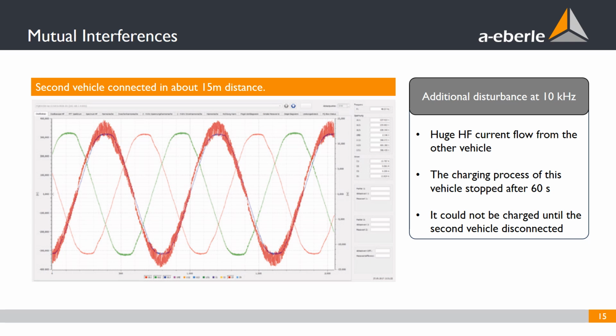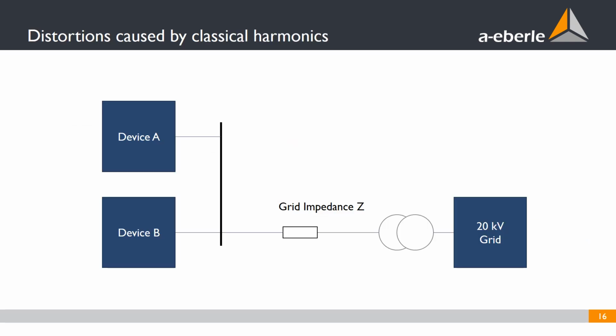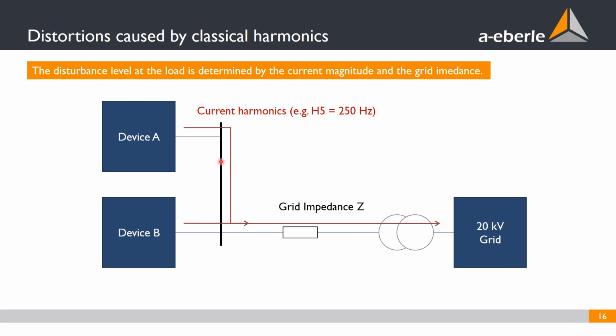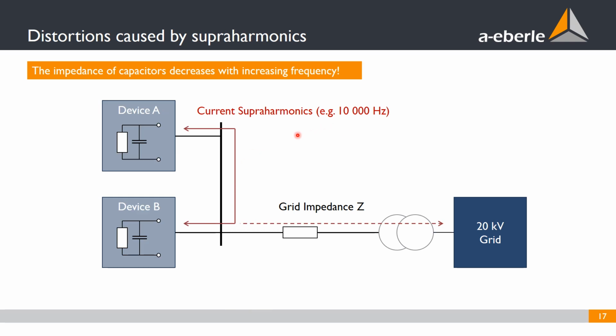This has something to do with the general characteristics of supraharmonics in comparison to general harmonics. In general harmonic analysis, if you have two devices connected together to the grid, they are going to produce a specific frequency, and the current with this frequency is going to flow through the grid impedance and cause a distortion here. With supraharmonics, at higher frequencies, the special thing is that all of these devices have capacitors inside, and the impedance of these capacitors decreases with increasing frequency. So the higher the frequency, the more these disturbance currents tend to flow back to the other devices. So you have a current flow between the devices, and you will not see much current at the transformer, because the inductive characteristic of the transformer is going to damp everything down.